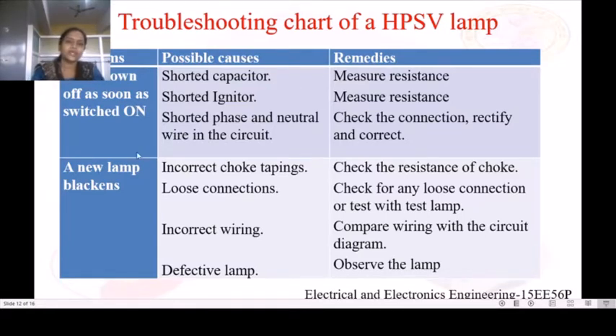Next problem, the new lamp blackens. For this problem, the possible causes are: first one, incorrect choke tapping. For this, we need to measure the resistance of the choke coil using a multimeter. If the resistance is 0, then there is a short circuit in the choke coil. If there is a resistance, then we say that the choke is in good condition. Loose connection. For this, we need to check for any loose connection in the circuit, or we can also test the continuity of the circuit using a series test lamp.